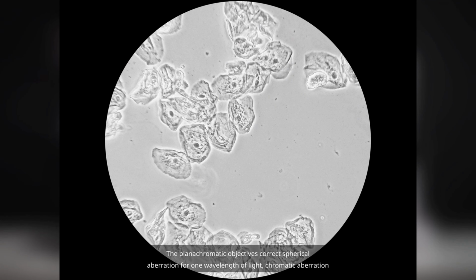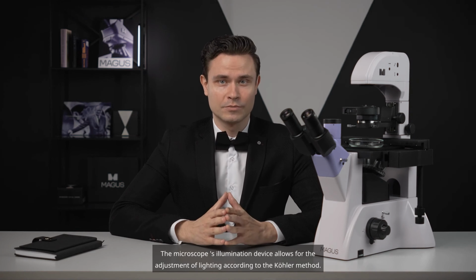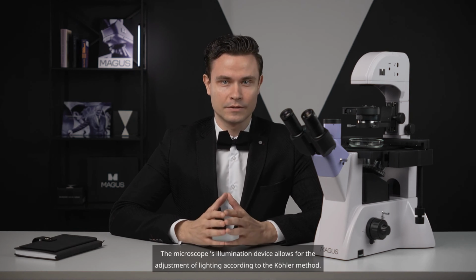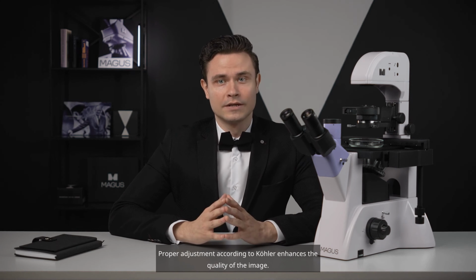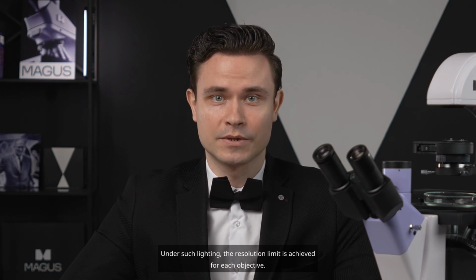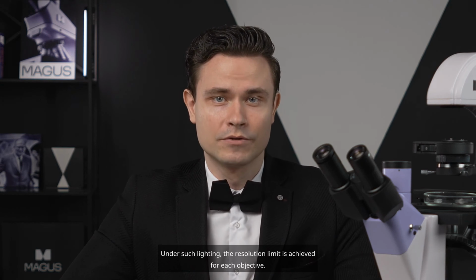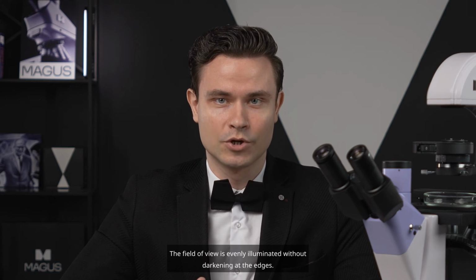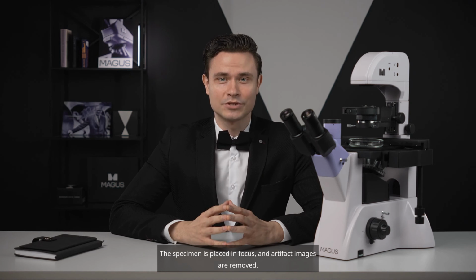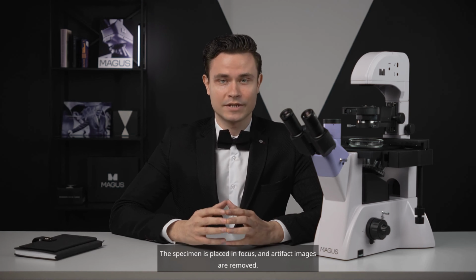The planachromatic objectives correct spherical aberration for 1 wavelength of light, chromatic aberration for 2 wavelengths, and correct field curvature by 90%. The microscope's illumination device allows for the adjustment of lighting according to the Köhler method. Proper adjustment according to Köhler enhances the quality of the image. Under such lighting, the resolution limit is achieved for each objective. The field of view is evenly illuminated without darkening at the edges. The specimen is placed in focus, and artifact images are removed.